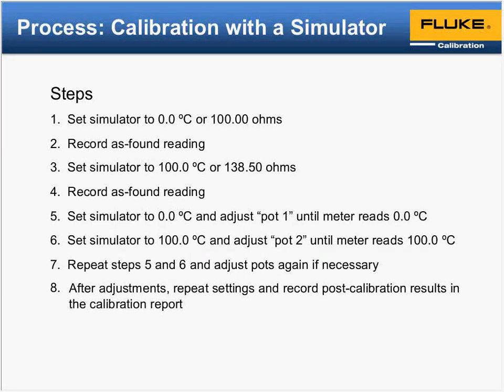Scenario, I guess, and things we'll kind of go back to in the Q&A. In this method, could the calibration that we did be considered traceable? That's one thing to consider. If it is to be traceable, those sort of steps must be taken with the references to be traceable. So, I don't know if we jump, but talk to these for a moment. Is this considered a traceable system? I would say no. The system electronics is probably dependent upon your simulator. In this scenario, the simulator already has a traceable calibration.